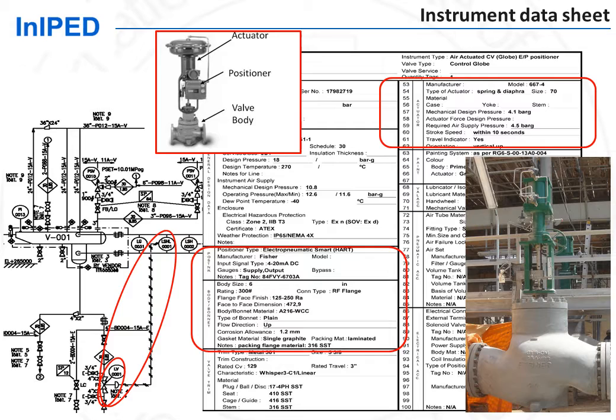It produces the instrument data sheet, also called instrument mechanical data sheet. It shows, for the body, the types of materials to be used for the body and the trim, the type of end connections — information specified by piping. So instrumentation gets this information from piping. It also specifies the type of actuator, as well as the type of positioner, and the type of signals that will be exchanged between the instrument and the control system.